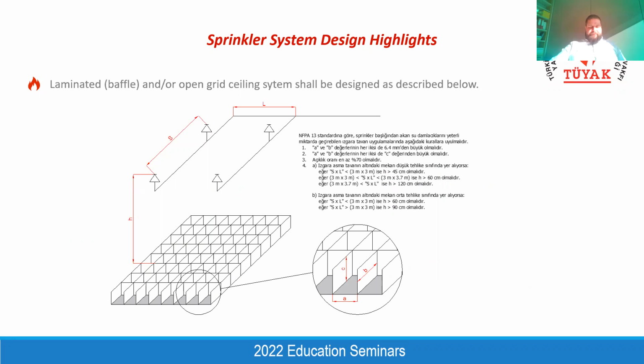And also, sorry. Also, in the latest projects, we are always finding open grid ceilings, laminated and baffle ceilings within the project, and architects are not preferring to see the sprinkler head beneath this decorative ceiling. We have some rules to omit these lower level sprinkler heads while designing this kind of open grid or laminated baffle ceilings. Architects should also know that, because the level of the suspended ceiling affects whether a sprinkler is required beneath the suspended ceiling or not. For example, you have a ceiling here. It's the concrete ceiling. And then you have a decorative laminated suspended ceiling here.